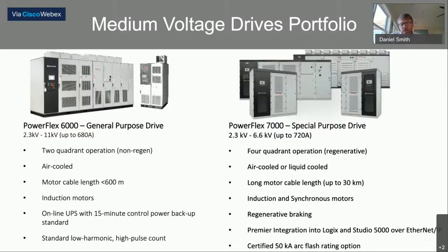It does not have a pulse width modulated output like other drives. The signal that comes off of it is a sinusoidal signal and can run cable lengths up to 30 kilometers. It also has the ability of running induction motors and synchronous motors. And as far as an induction motor, it doesn't have to be an inverter rated motor because it doesn't have that pulse width modulated signal.